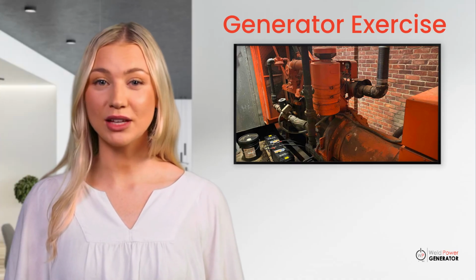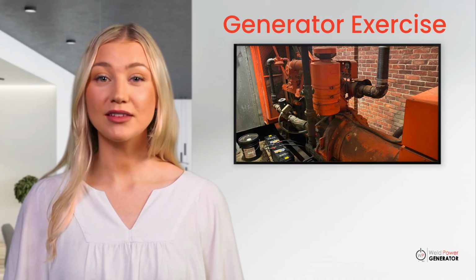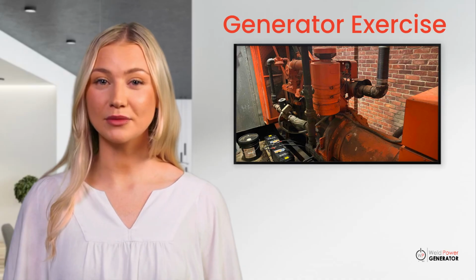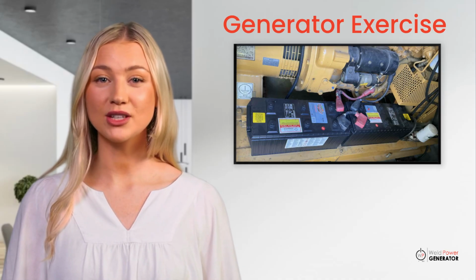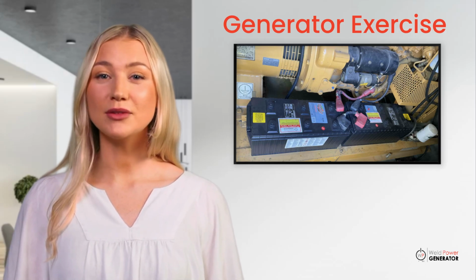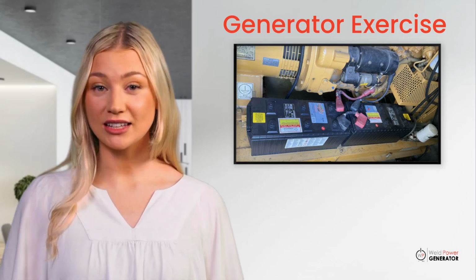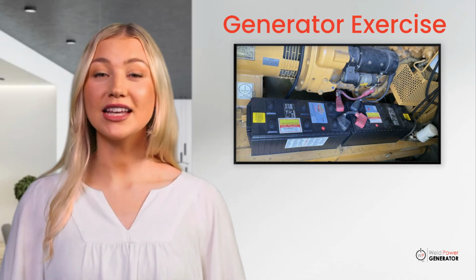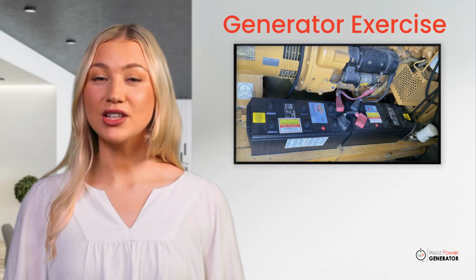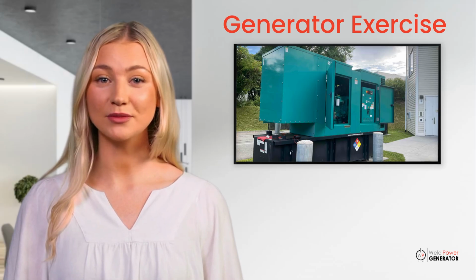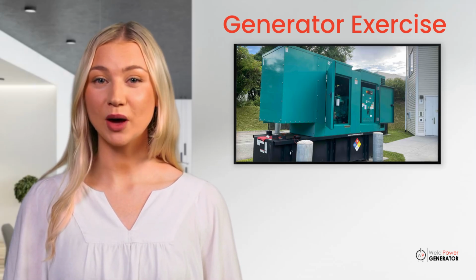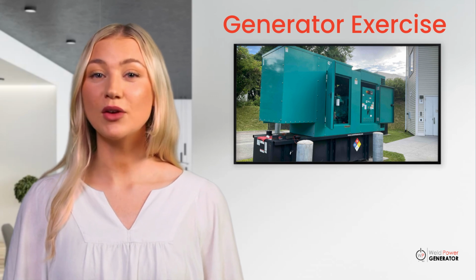A standby generator that sits unused for months is one of the fastest paths to premature failure. Fuel degrades, batteries lose their charge, rubber seals dry out, bearings corrode. The machine that was supposed to protect you in an emergency quietly loses its ability to do so. The solution is regular, loaded exercise runs, typically monthly, for a minimum of 30 minutes with a load.